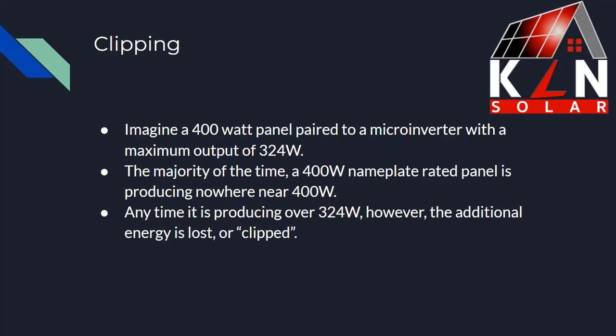So what is clipping? Imagine you have a 400-watt panel. The microinverter most commonly picked for it has a maximum output of 324 watts. The majority of the time, this 400-watt nameplate-rated panel is not producing anywhere close to 400 watts. But if at any point it's producing more than 324 watts — which is very possible and even likely on a south-facing panel in a southern state with good sun intensity — that additional energy, anything over the rating of the microinverter, is lost, or we call it clipped.